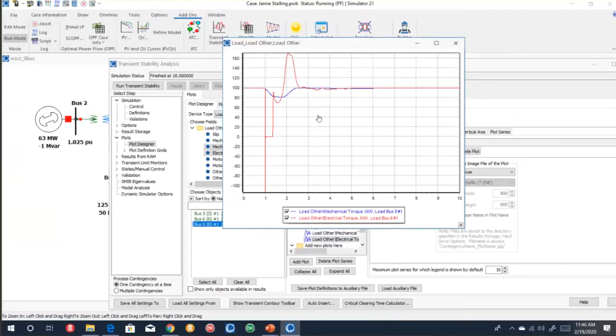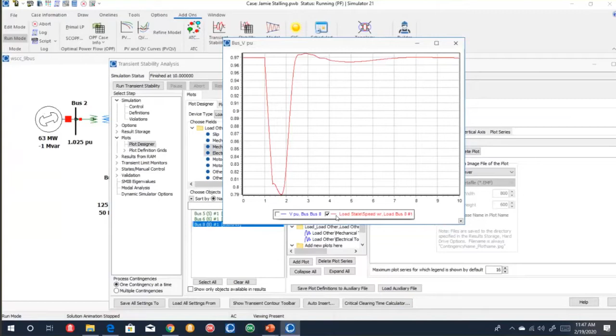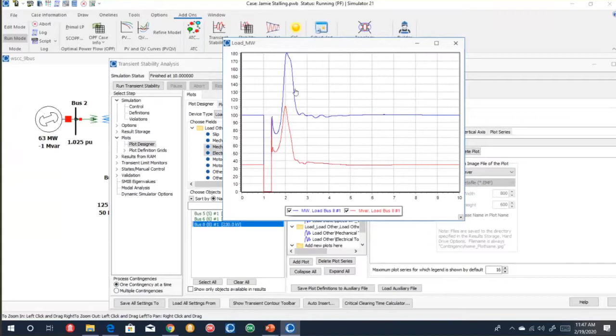And then the fault clears, and then you get a huge spike up in the electrical torque because it's trying to speed back up. It's trying to unstall itself or prevent itself from stalling. So what does that look like for the speed? The speed goes down, fault clears, and then it starts going back up. And then the interesting thing that we care about is, well, what does the load look like during this? So the load started out as 100 megawatts and 34 or 35 Mvars. In order to re-accelerate itself, the red is the Mvars and the blue is the megawatts. You end up having a big spike in power in order to accelerate yourself back up and then settle back out to a new steady state.